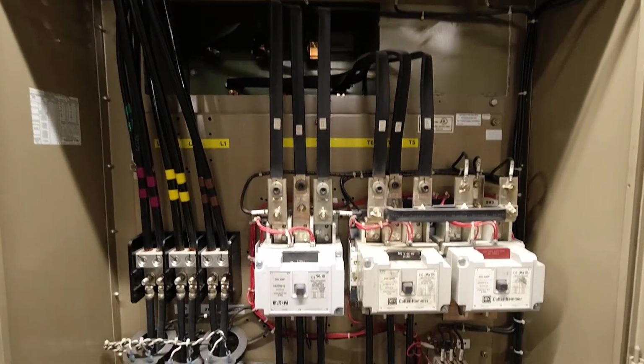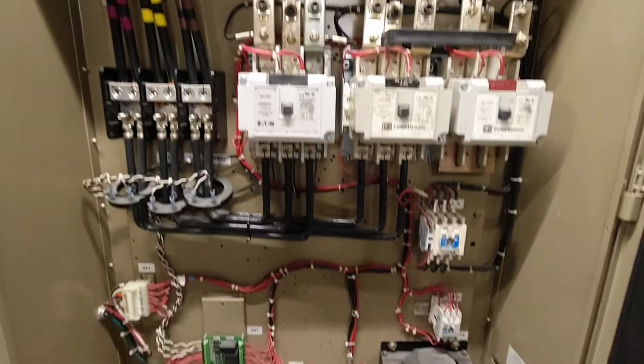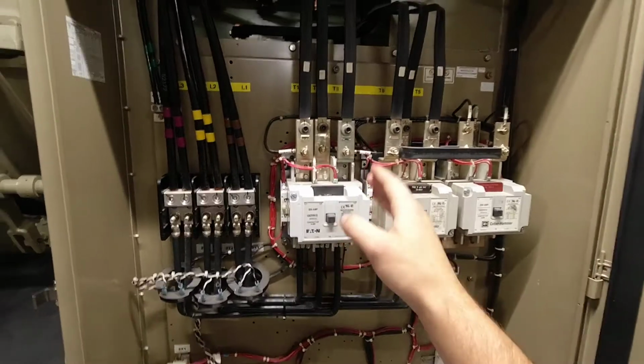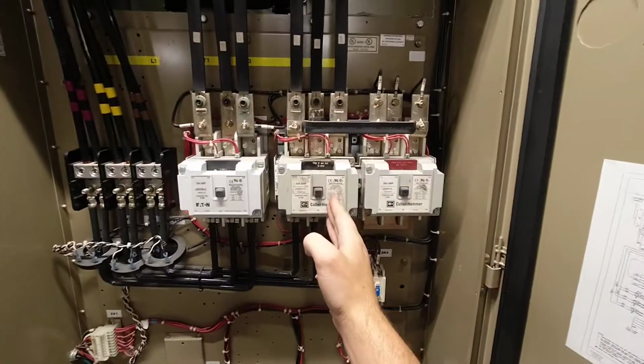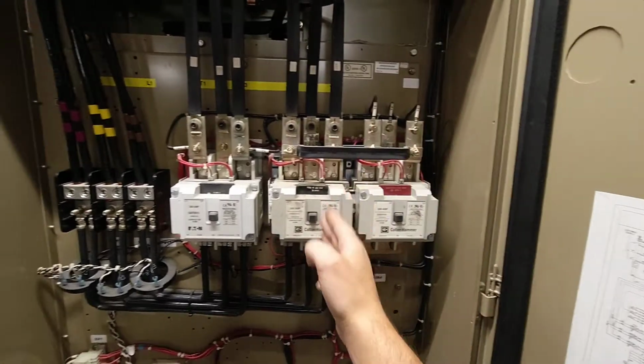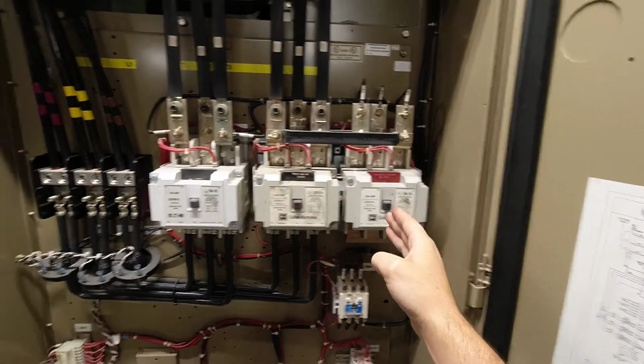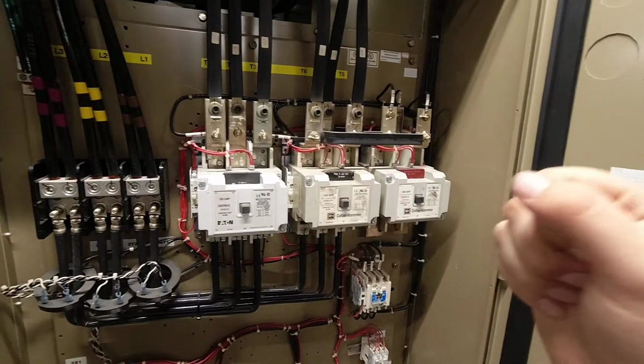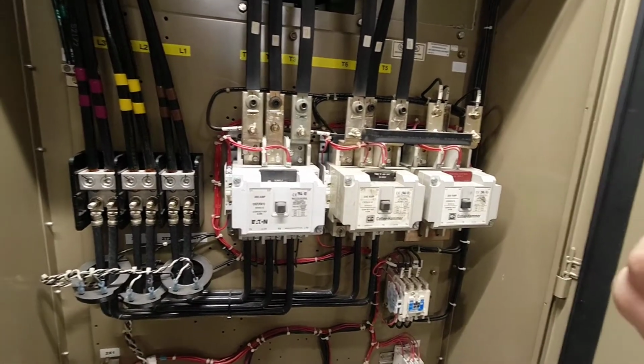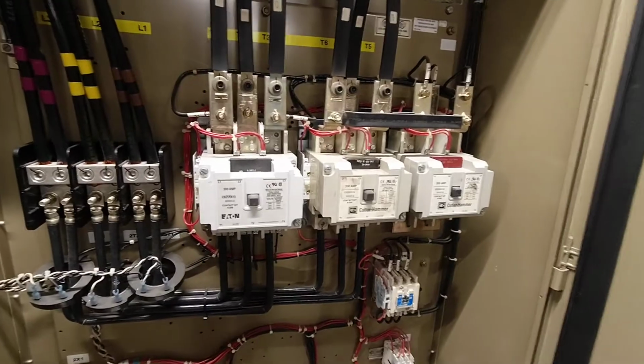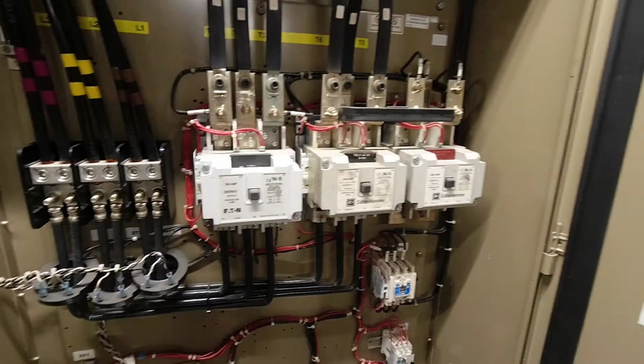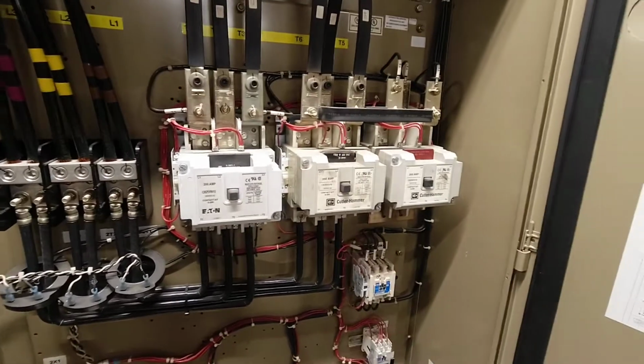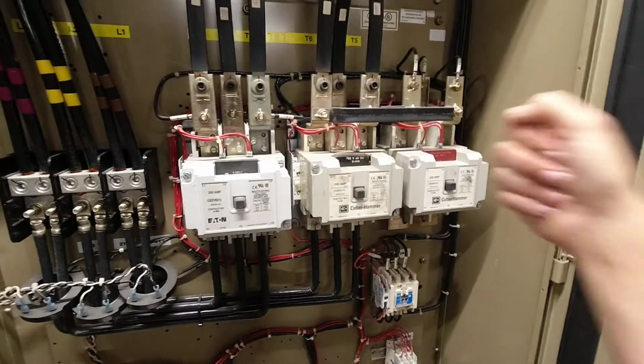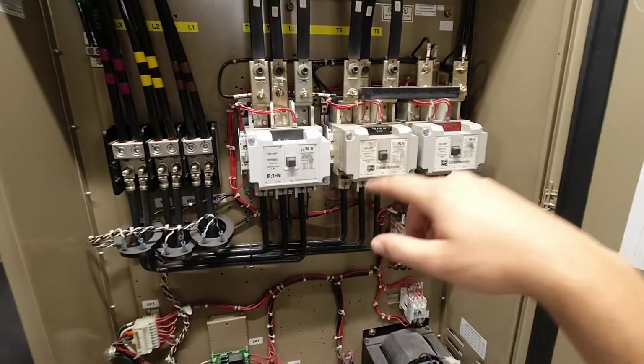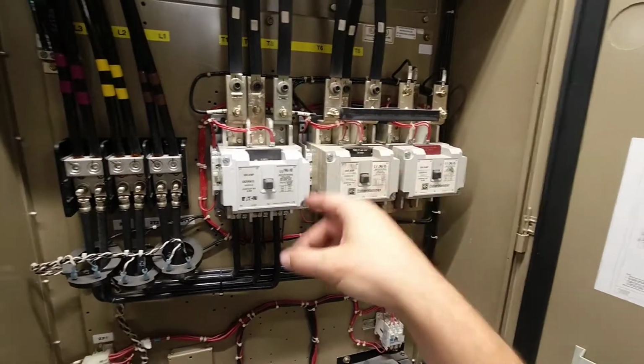So up top there, you've got the resistors that help with the starting circuit. And this is a Y-delta start sequence. And so this is your primary, your secondary or your run, and then your start contact. So what you'll see happen is, if I remember correctly, the pattern is it hits the primary, releases, hits the start, and then the primary hits and holds, and then the start releases and the secondary engages. And anyway, it cycles through that process.